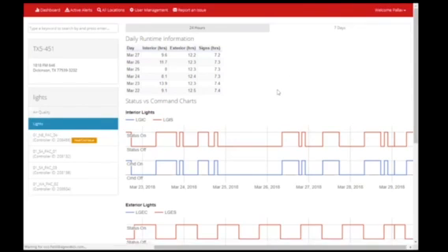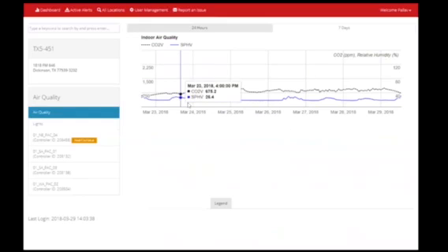The last interesting chart over here would be the air quality chart. So you can see the humidity and CO2 being measured and monitored. They seem within reasonable values. CO2 at about 800 is a little bit higher than people tend to like, but it's within reason. And humidity is a little low, but that's probably just the weather down there since it's Texas.